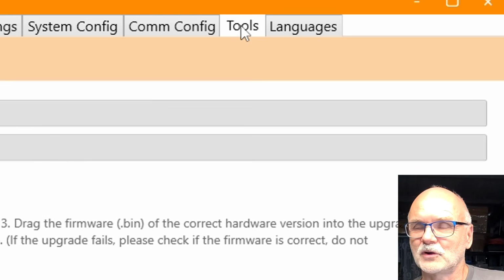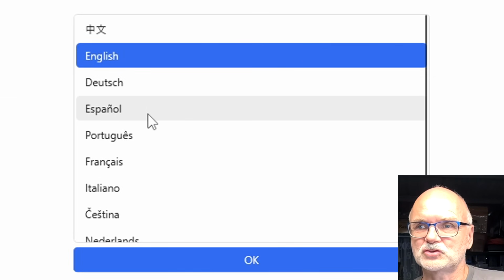I think this is all the BMS can give us at the moment. There's also tools, the BMS Upgrade, and languages, which can also be in Deutsch or Espanol. So you can see they're going in the right direction. They've got the full charging algorithm now included here with rebulk at a certain state of charge of your battery. You can set a charge voltage independent of the protection voltage. It does a float voltage, which is the same value as the pack overvoltage recovery.